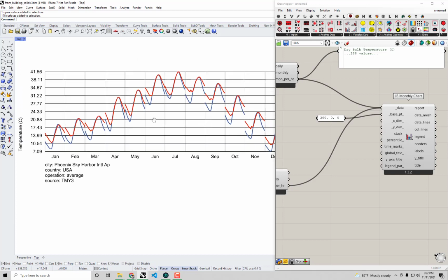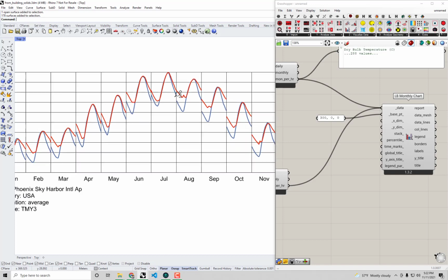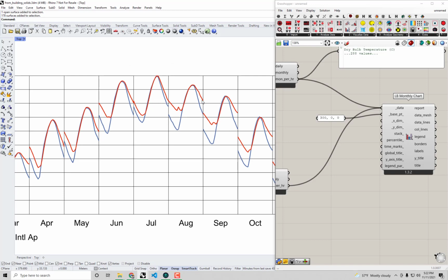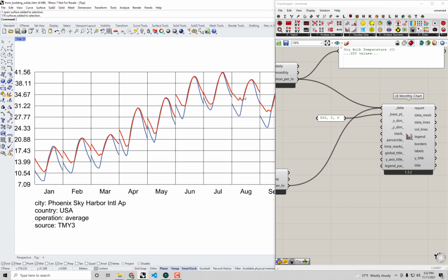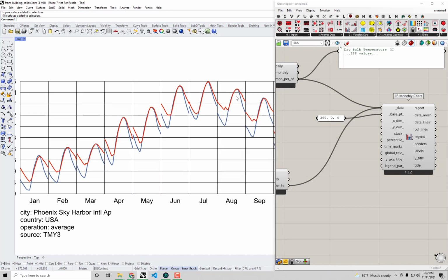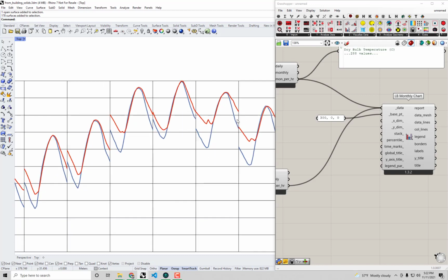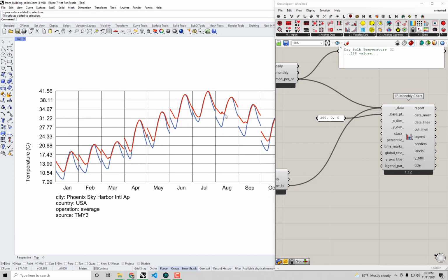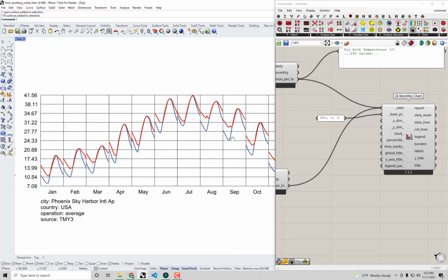Probably we can see the area where the urban heat island effect makes a really big impact is, let's say, in a month like August, right? Because we can see what's happening here for our district. Wow, we almost get, again, that temperature difference of close to 5 Celsius between the urban temperature at around 5 or 6 a.m., right before sunrise, and that rural temperature. So we can imagine, right, especially when the temperatures are around 36, if the urban area is staying around 34 degrees Celsius instead of cooling all the way down to 28, right? That's going to have a noticeable impact on our air conditioning load, I'm sure, over the course of our nighttime in Phoenix.